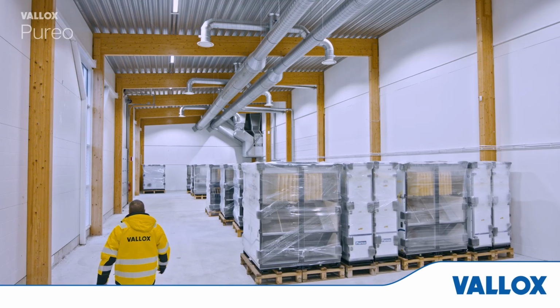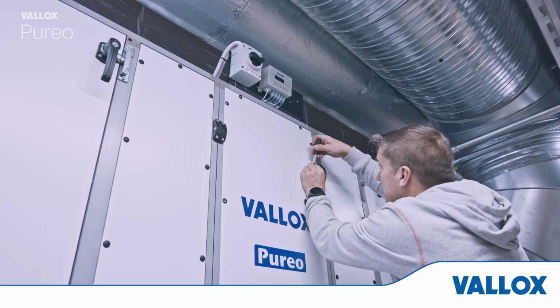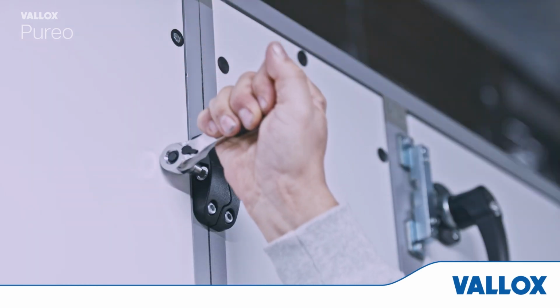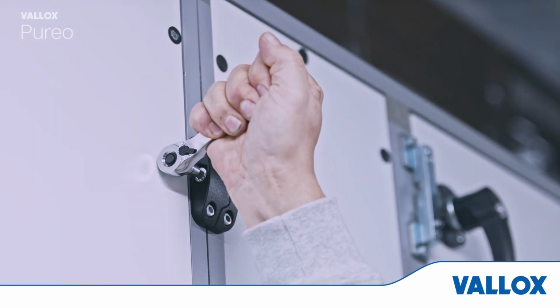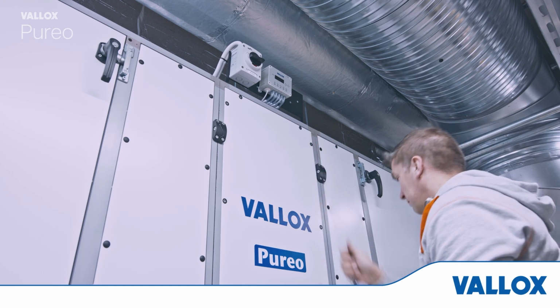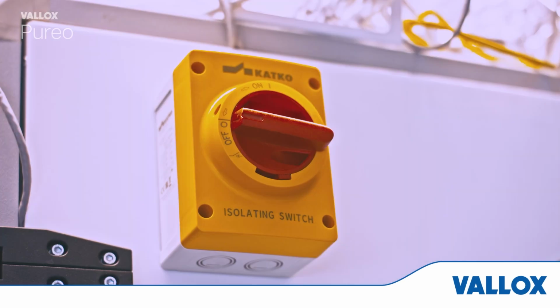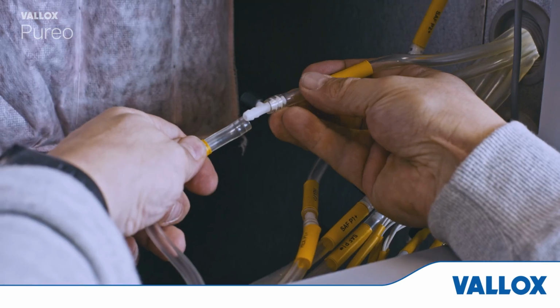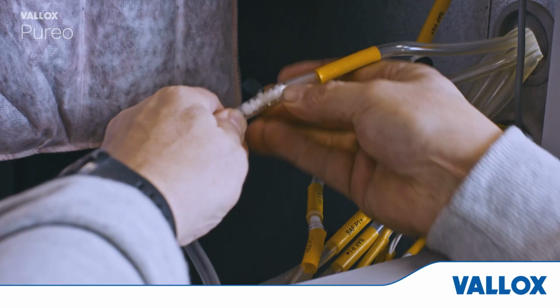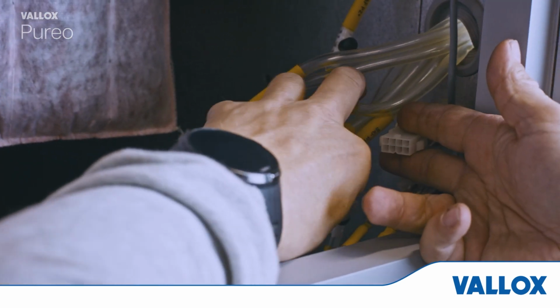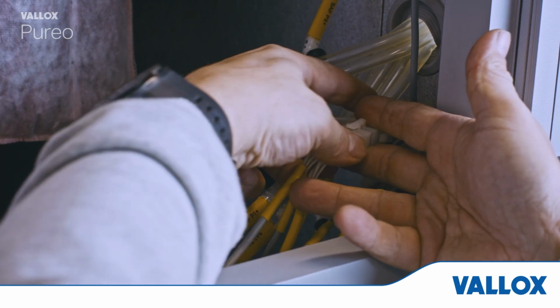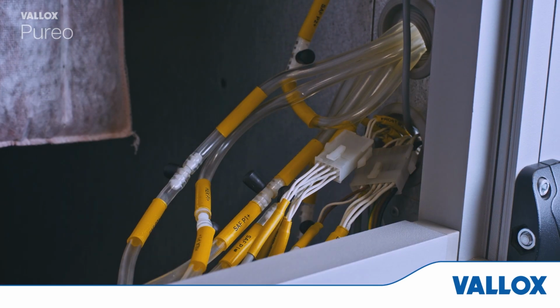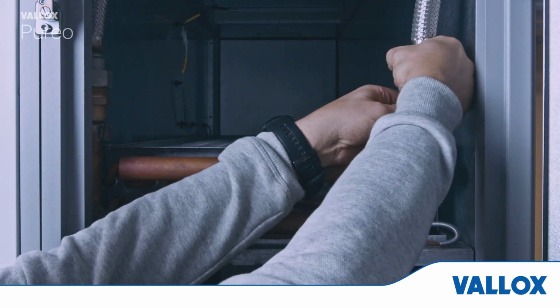The larger unit models are delivered in modules. Before assembling the unit, place the modules close to each other and tighten with screws. This allows you to connect the tubes and electric wires easily and ensures clean assembly. Before starting electrical installation, always make sure that the unit is not connected to the mains. Check the electric connections and make sure the pressure tubing has been connected correctly according to the markings. Tighten the radiator tube couplings.